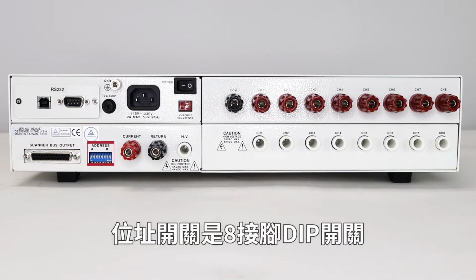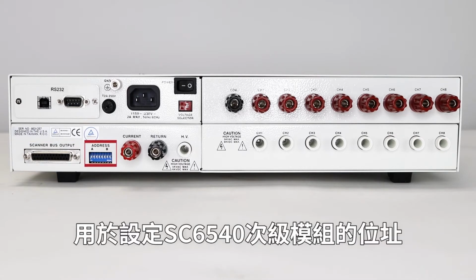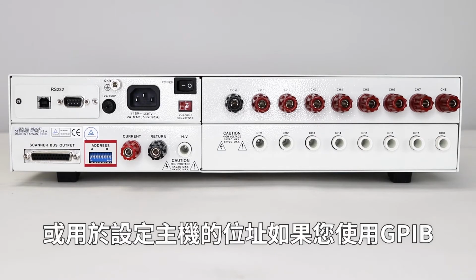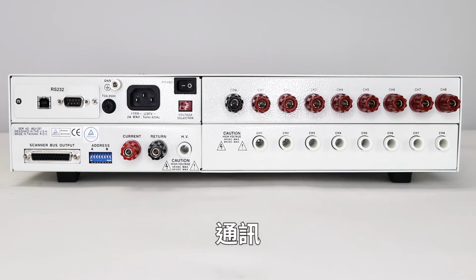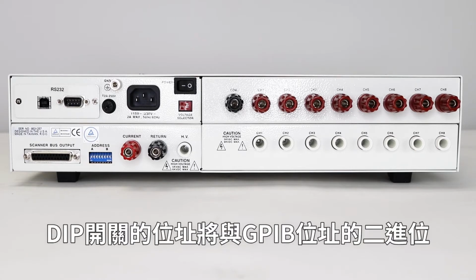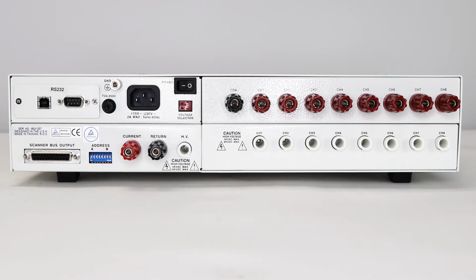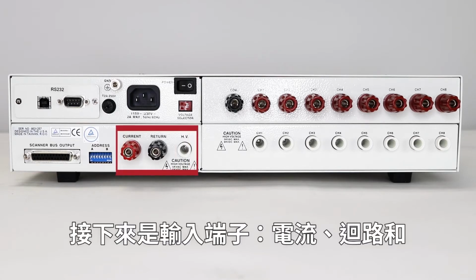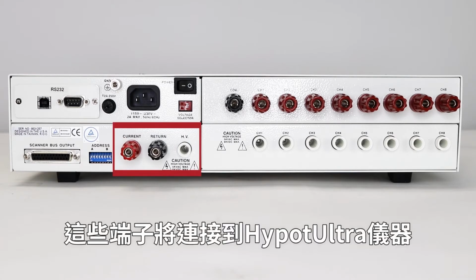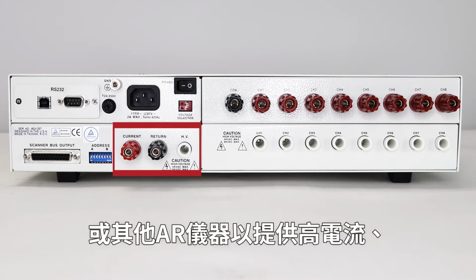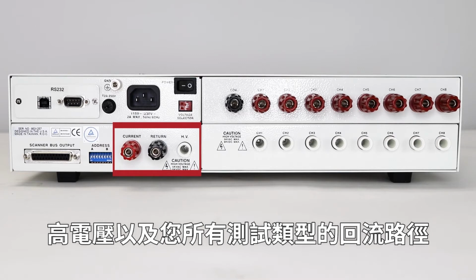The address switches are 8-pin dip switches that are used to address modules in the SC6540 secondary, or used to configure the address of a main should you use GPIB communication. The dip switch's address will be the same as the GPIB address in binary. Next are the input terminals: current, return, and high voltage. These terminals will either connect to the HypotULTRA instruments or other AR instruments to provide high current, high voltage, and a return path for all your test types.